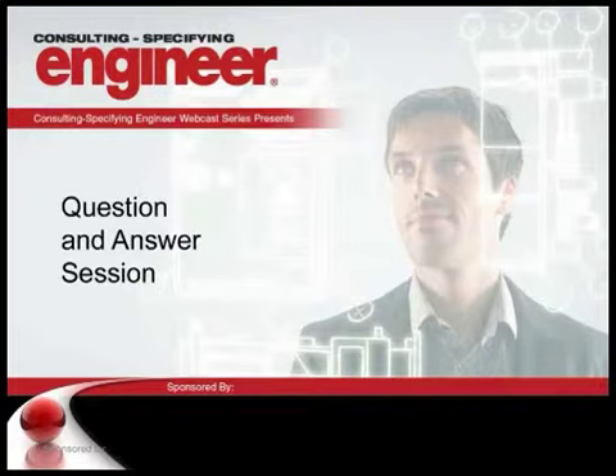Circuit breakers with adjustable trip settings, what we call variable functions, can be programmed to not have an instantaneous function, and that's a common way to arrive at selective coordination, which is to turn off or not have an instantaneous function on the circuit breaker ahead of the transfer switch. But in doing that, you expose that switch to a fault current that might exceed its withstand time. So I'm not sure if that answers the question, but that's my attempt.